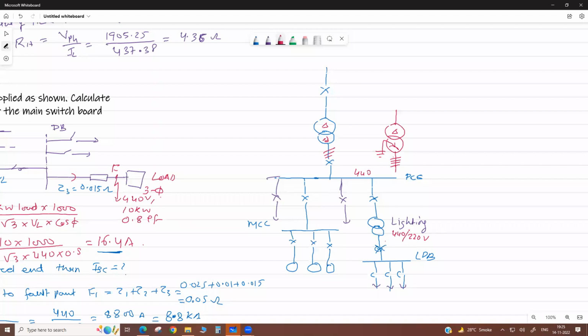We get the desired voltage. But for your knowledge, I will explain. See, now in commercial utilities also, like in malls and industries, it is now a usual practice to use the lighting transformer, even though this is a 3-phase 4-wire system also. There are two purposes. Generally here it is not 415 volt. It is 220 or 240 volt also.